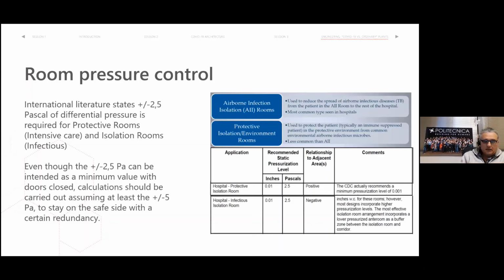However, in our application, we have applied not 2.5 Pascal to calculate the flow rates and the flow rate difference between supply and return. We have assumed plus or minus 5 Pascal, according to whether it is a protective or isolation room. So this is to stay on the safe side, because you know it is very frequent that there are some cracks or imperfections in the envelope. So we must have a certain redundancy in the flow rates. So if we start with 5 and it's okay, we should get 5, but at least we must not go below 2.5. This is the minimum, absolutely the minimum.